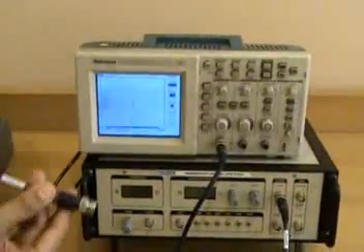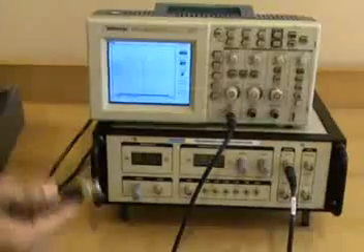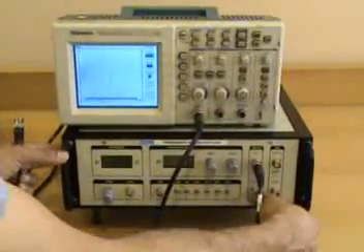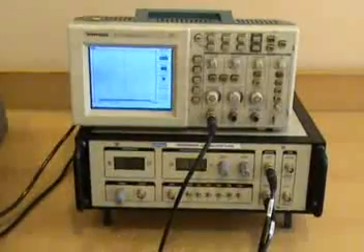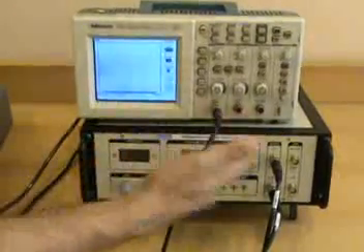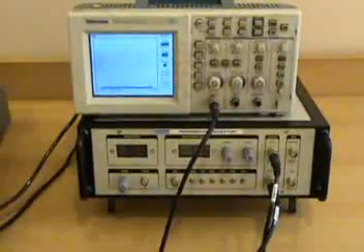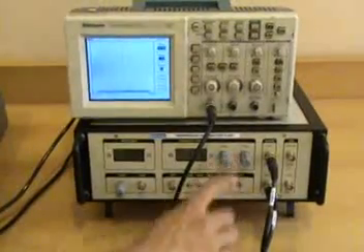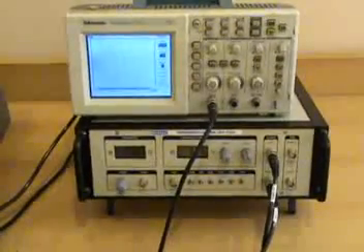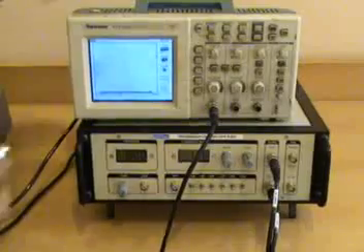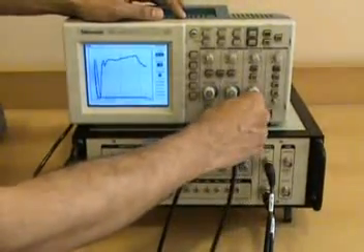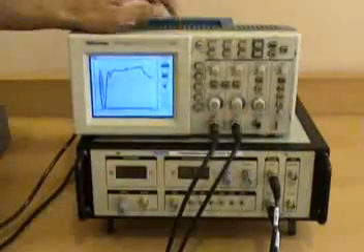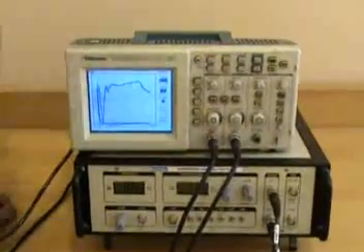Then there is another XY cable which is connected to vertical output. Vertical output is nothing but DC output of the frequency which is displayed here. There is basically a detector inside it which converts the RF frequency into DC voltage. Now this output vertical is connected to the Y channel or channel 2. Now what you see is a frequency response.